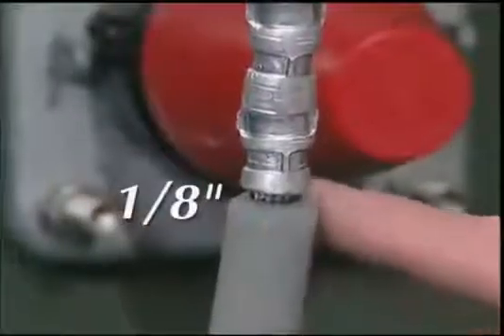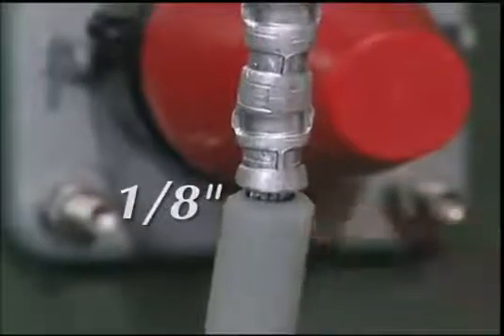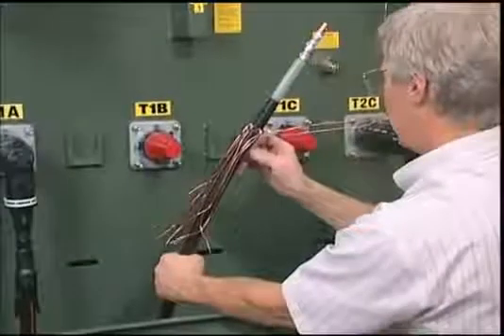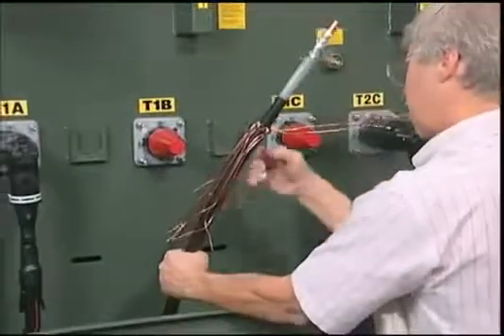Next, put a 1/8 inch chamfer on the end of the insulation. This chamfer reduces the installation force. Now, bend the shield wires out. Then clean the cable jacket using a lint-free cloth.